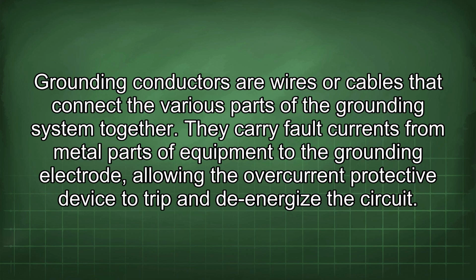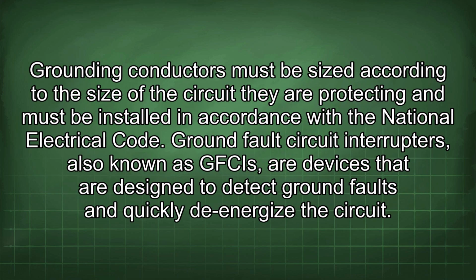Grounding conductors are wires or cables that connect the various parts of the grounding system together. They carry fault currents from metal parts of equipment to the grounding electrode, allowing the overcurrent protective device to trip and de-energize the circuit. Grounding conductors must be sized according to the size of the circuit they are protecting and must be installed in accordance with the National Electrical Code.